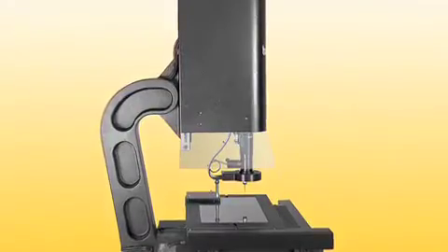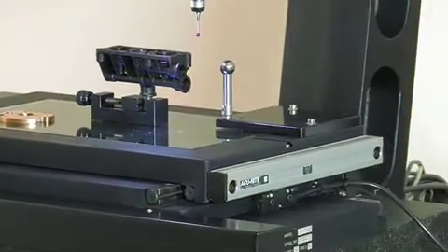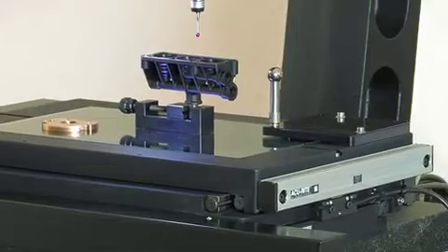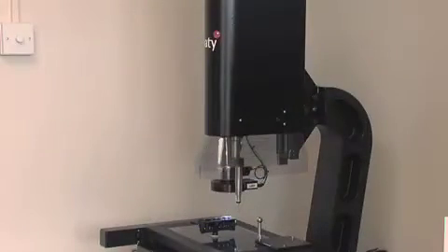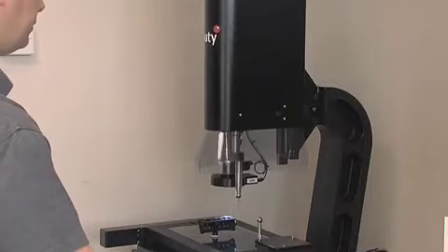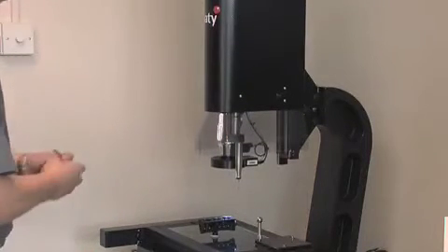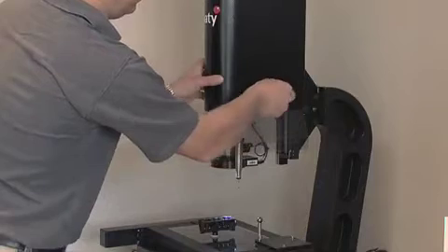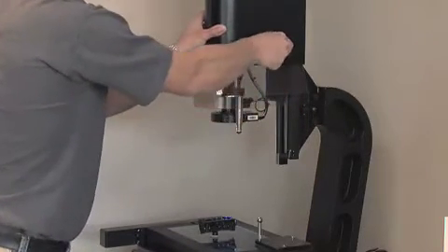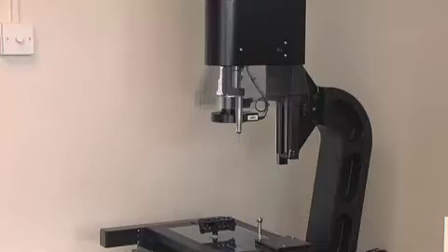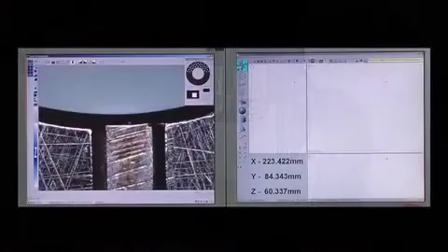The heavy-duty XY stage is CNC machined from billet and assembled using the highest quality cross-roller rail guides for optimum precision. The Z-axis utilizes a cast steel bearing system and a novel dovetail slide mounting that enables the user to lock the headstock anywhere in a 100mm range, in order to allow for fixturing whilst retaining the 165mm measuring range.